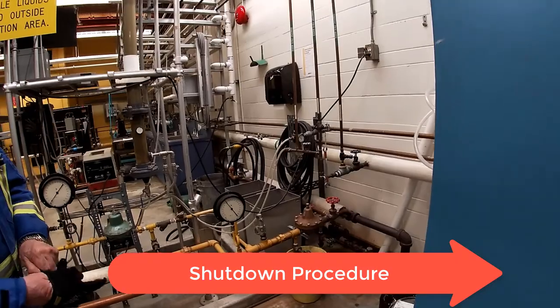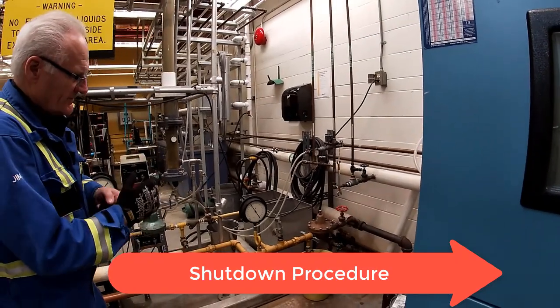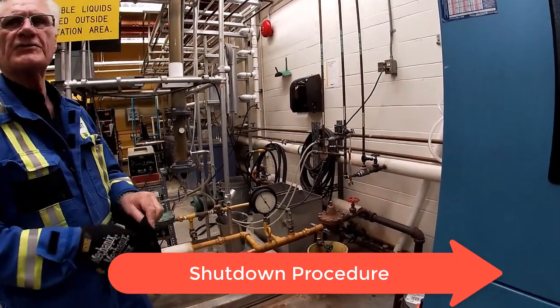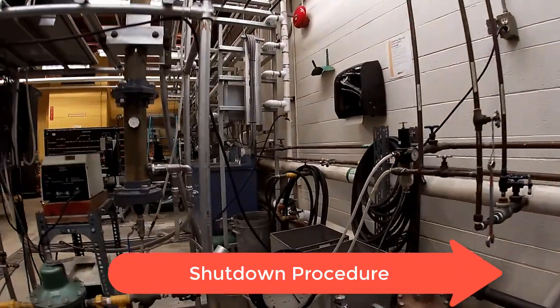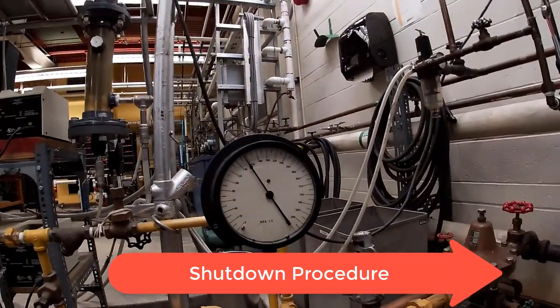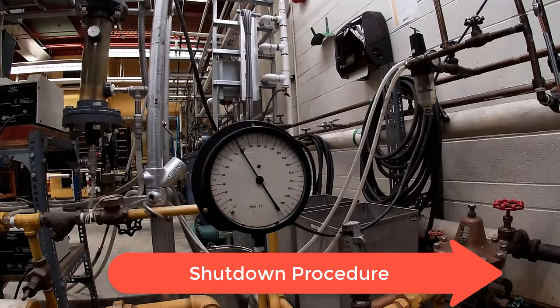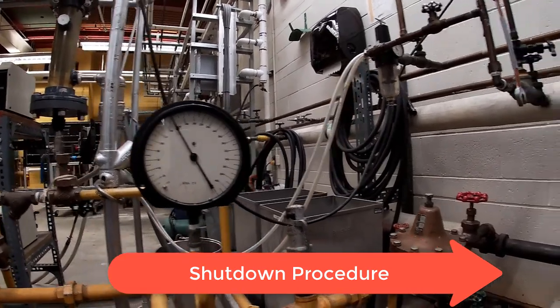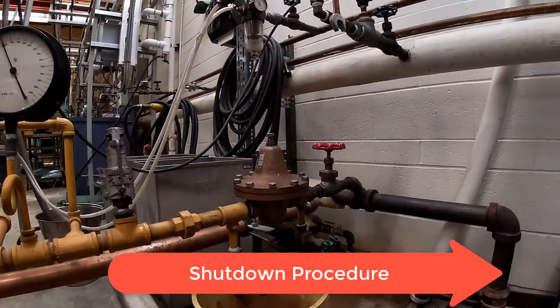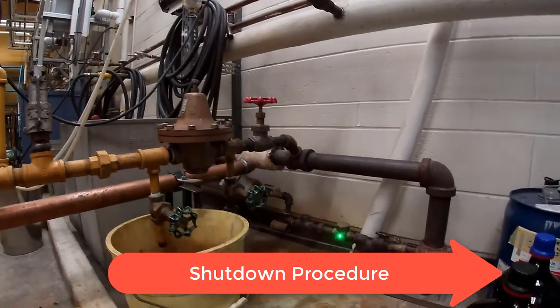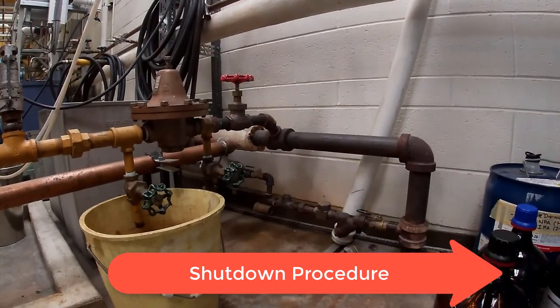Okay, so we're going to sit over here at the steam regulator and wait until we see the steam pressure starting to drop, which may take quite a while. If you heard that little click in the background, that was the thermostatic trap right there that opened up a little tiny bit to let any condensate out.